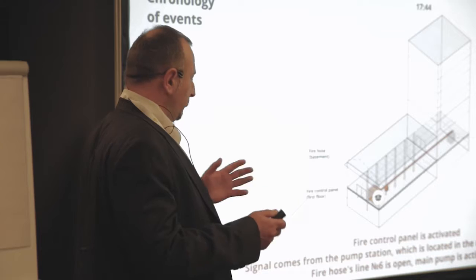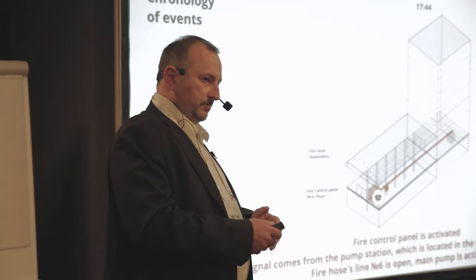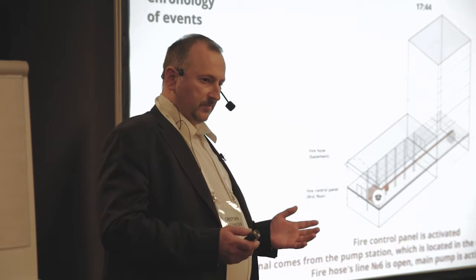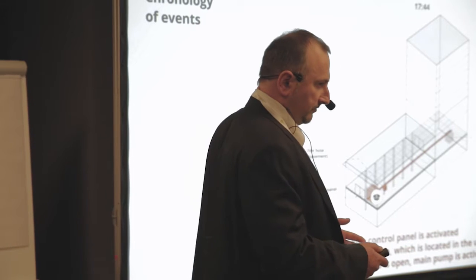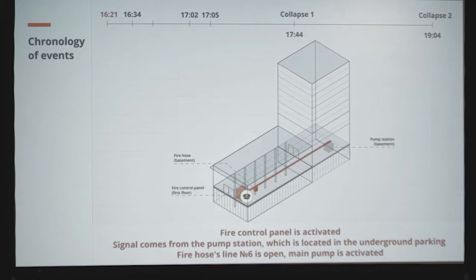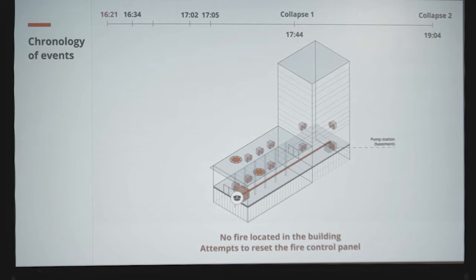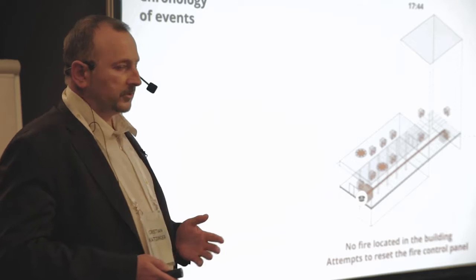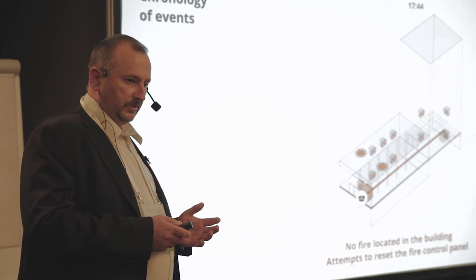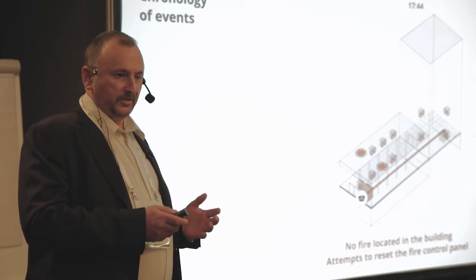Line 6, which is located for the system in the basement. There's a signal, the valve is open. Because the valve is open, the contact was lost and it came to a fire alarm. And because of this, the automatic voice alarm system went on. The smoke exhaustion system went on, and the normal ventilation went off. But there wasn't any fire inside the building, so it had to be a false alarm.